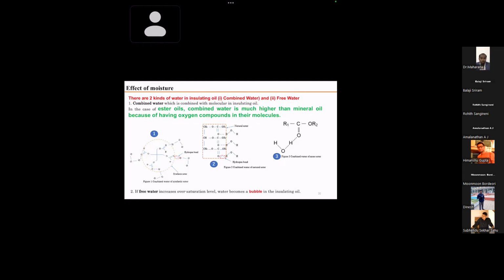There are two perspectives to this problem. First, if you want to deploy ester oil and change the whole transformer design, coming from a mineral oil standard transformer to an ester oil standard transformer, there would be much more effort and labor required by the industry to make such an ester-oil-based transformer. Rather than that, what we suggest is changing the oil parameters so it can be accommodated in the existing transformer, or adding some attachment to the old transformer to generate circulation, for a viscous oil such as FR3.